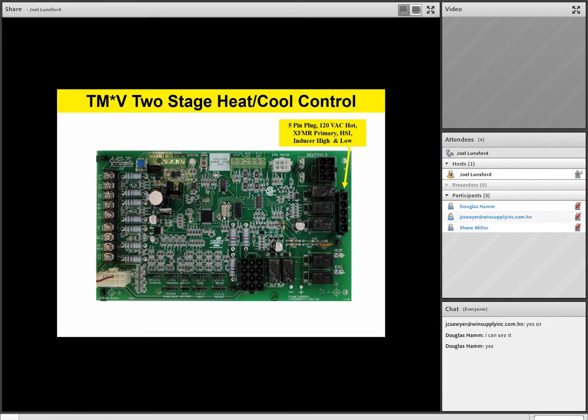Right below that, you have a humidifier terminal for 120-volt output to a humidifier on a heating coil. Right next to that, you have an EAC terminal for the electronic air cleaner if it's so equipped. Now remember, team, anytime I have a G call or a fan call generated on this board, it's going to output 120 volt for an electronic air cleaner if so desired.